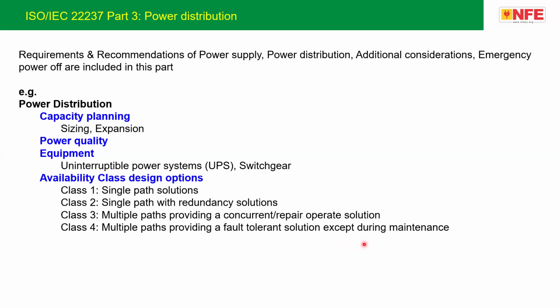So when we move to equipment selection, UPS is the main component in the data center. The UPS should be designed with respect to how it feeds the IT racks in the normal scenario and how it will be fed during bypass mode. And the switchgear should be designed with respect to the IEC requirement for the fault current, and the temperature we get at the terminal, depending on how the connection is made.